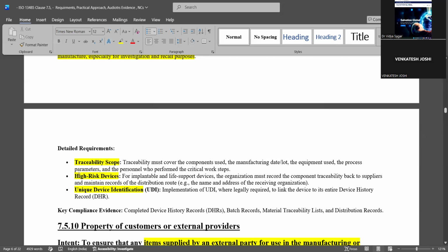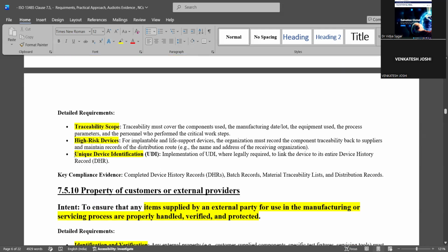Okay, and I told you for high risk devices, you need to maintain the traceability. I said traceability must cover the components, manufacturing date, equipment, the parameters, personnel, high-risk devices, implantable life support devices, the organization, component traceability to suppliers, to storage, name and address of the receiving organization. And for that, the important thing is you will have a UDI DI, or you can trace from the device history file, or in India, basically we trace it from batch manufacturing records. We call them BMR.